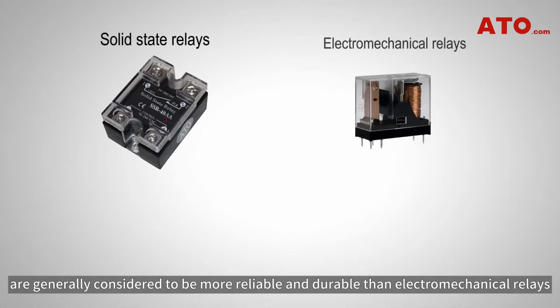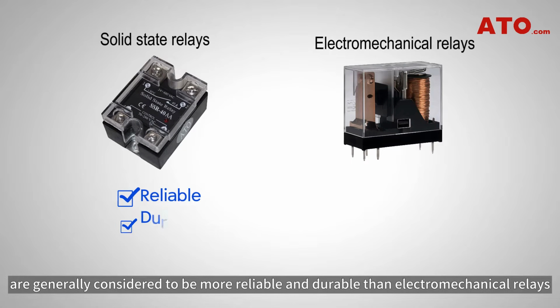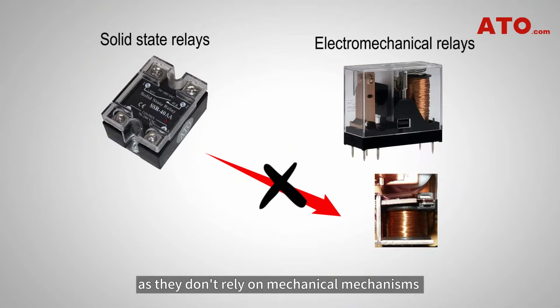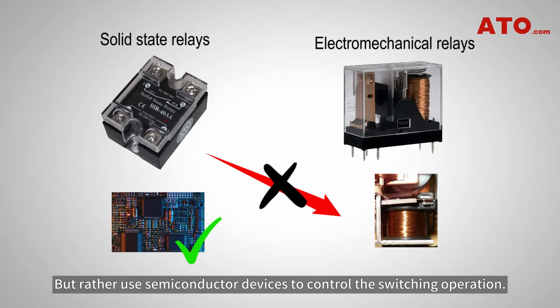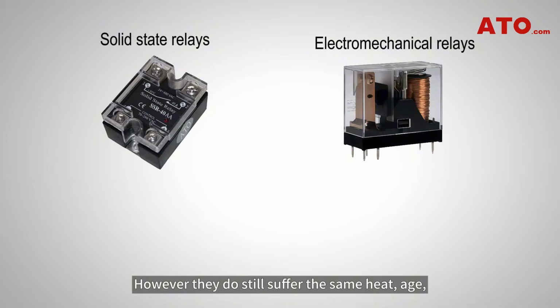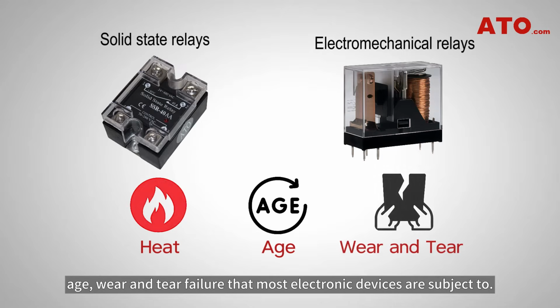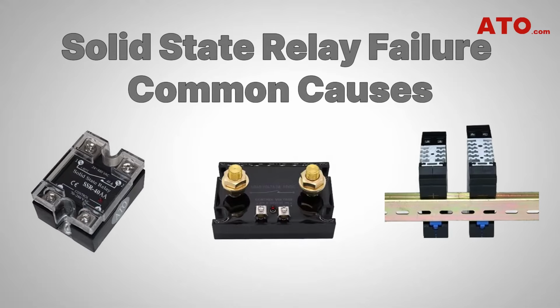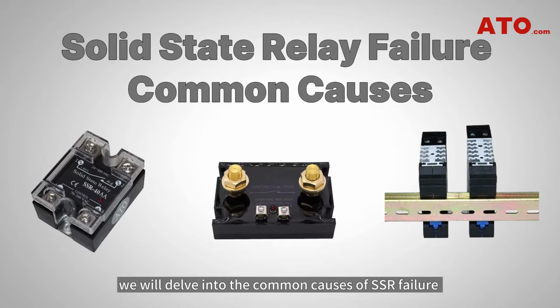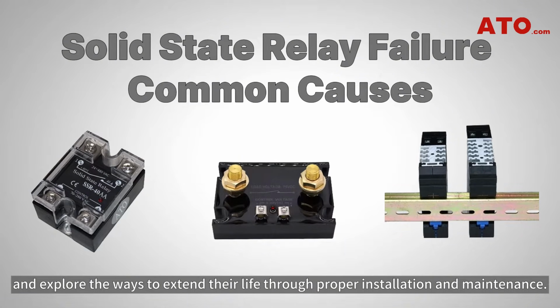Solid-state relays are generally considered to be more reliable and durable than electromechanical relays, as they don't rely on mechanical mechanisms like coils and contacts to perform switching action, but rather use semiconductor devices to control the switching operation. However, they do still suffer the same heat, age, wear, and tear failure that most electronic devices are subject to. In this video, we will delve into the common causes of SSR failure and explore the ways to extend their life through proper installation and maintenance.